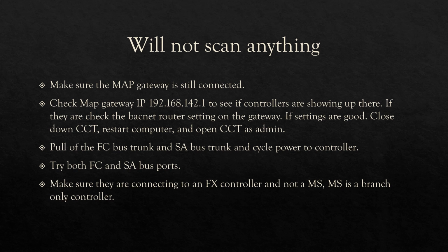And there was a batch of these Facility Explorer controllers that came out with the wrong firmware on them. You'll see that when you go to load it on the page, it'll say MS device and not F4 device.